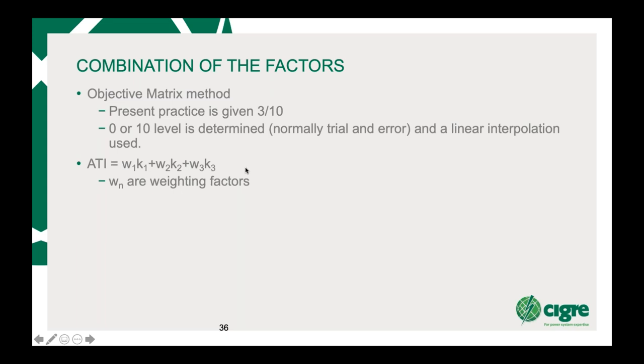And what we're saying here is it's actually called an objective matrix method, and it was used within the human resources area. But the present practice is that you take, say, you're using quad zebra or using triple tern conductors, give it a 3 out of 10, and then you determine what you consider to be a really good score. In other words, with a life cycle cost of $10 million, I'll make that a 10 out of 10 score. And then you use linear interpolation between the lot, and for any value, you can get a score out of 10. So that's really how it's done.